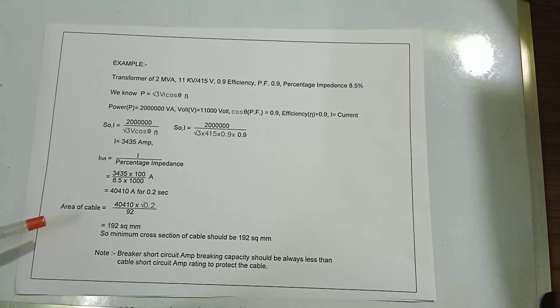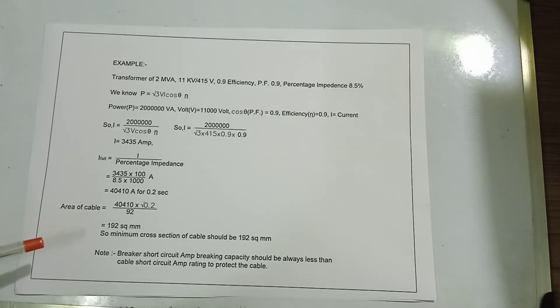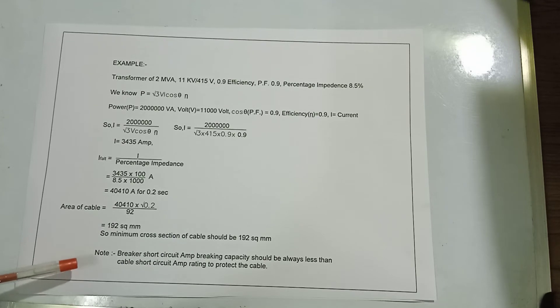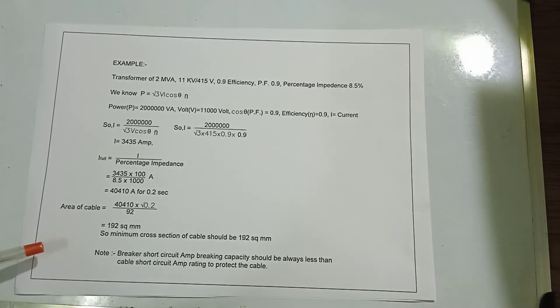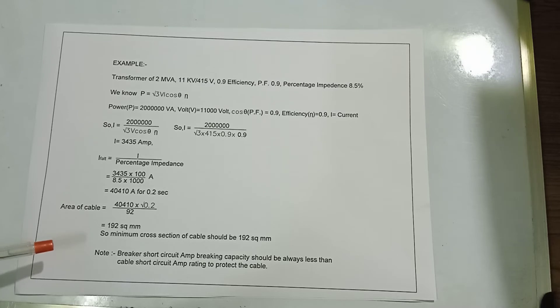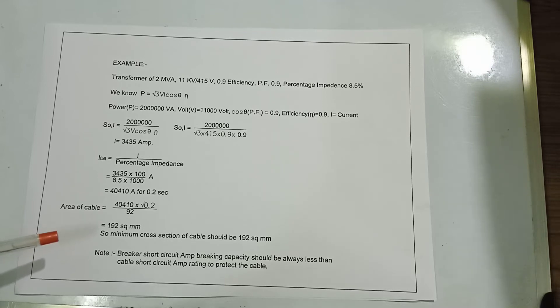When choosing HT cable cross section for short circuit current, never select a cross section below 192 square mm. Note: the breaker short circuit ampere breaking capacity should always be less than the cable short circuit ampere rating to protect the cable. If the breaker does not open in time, the cable will be damaged.